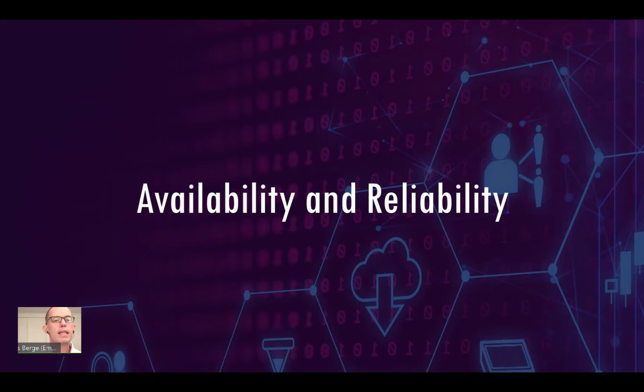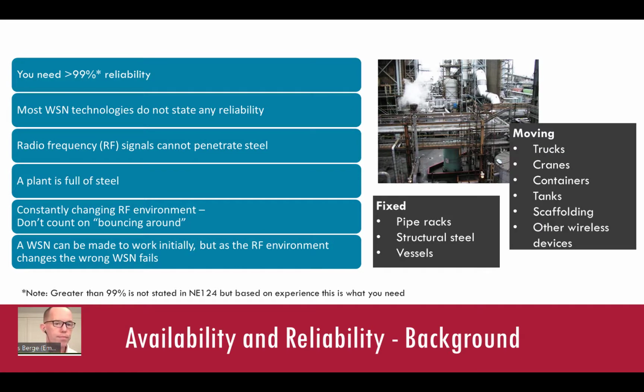The first requirement is availability and reliability, because this is probably the most important. You need greater than 99% reliability for the wireless sensor network in your plant to make sure the data is there when users need it. This number is not stated in NAMUR NE 124, but based on experience, 99% is necessary. Most technologies do not state any reliability. There's no commitment.